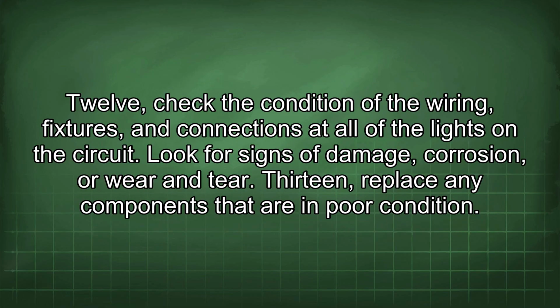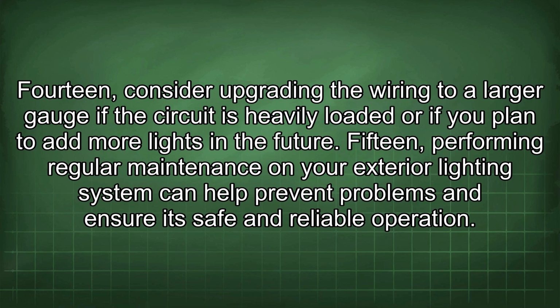12. Check the condition of the wiring, fixtures, and connections at all of the lights on the circuit. Look for signs of damage, corrosion, or wear and tear. 13. Replace any components that are in poor condition. 14. Consider upgrading the wiring to a larger gauge if the circuit is heavily loaded or if you plan to add more lights in the future. 15. Performing regular maintenance on your exterior lighting system can help prevent problems and ensure its safe and reliable operation.